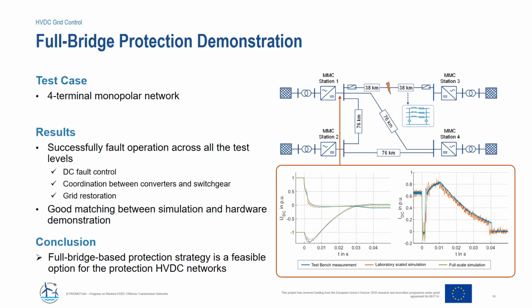The restoration process is not displayed here, but overall we can conclude that in all our test cases the DC fault control worked in the demonstration as well as in the full-scale simulation. The coordination between the converters and the switchgear worked as planned, and also the grid restoration worked as foreseen in the studies from work package 4. So overall there's a very good matching between the simulation and our hardware demonstration. And to conclude this, the full bridge demonstration seems to be a very feasible solution for the protection of HVDC networks.